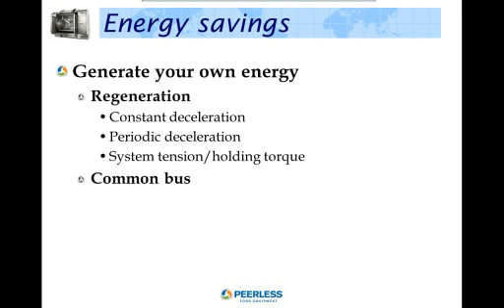Periodic deceleration. When a load is stopped quickly, the inertia of the load wants to keep turning, such as a large drum. In this case, the cycle time, or how many times a load is stopped over time, as well as the magnitude of the stopping power required, determines how much energy can be saved.